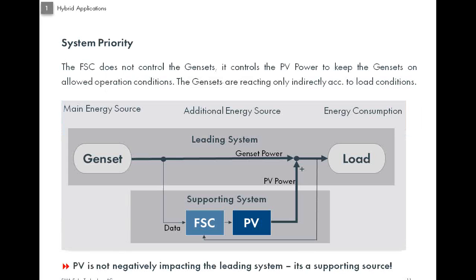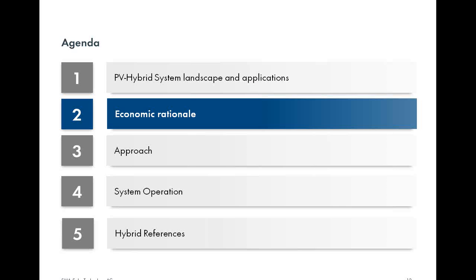Another way to look at it is that the PV is acting as a negative load, right? So when the PV is supplying power to the load, the genset sees that the load has become reduced. So it automatically decreases its capacity. So that's another way of looking at it.